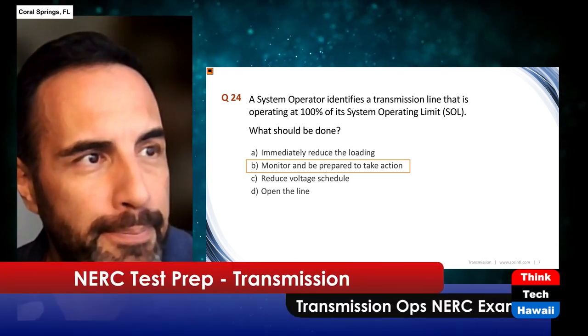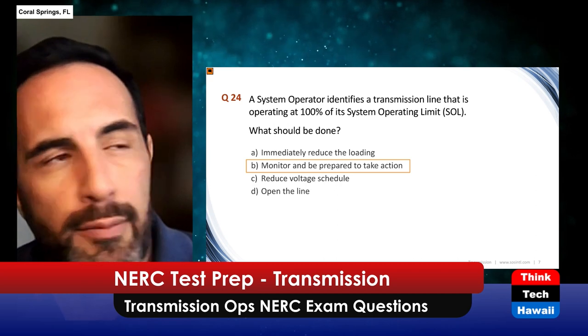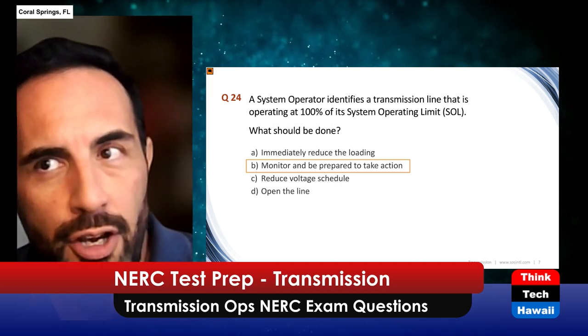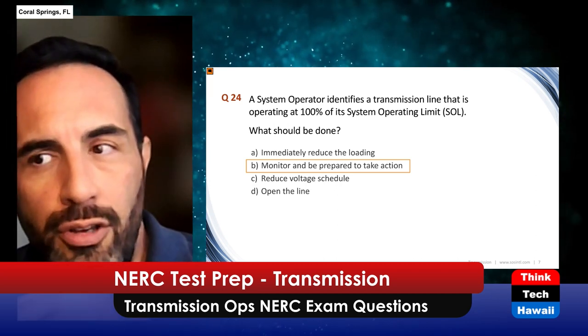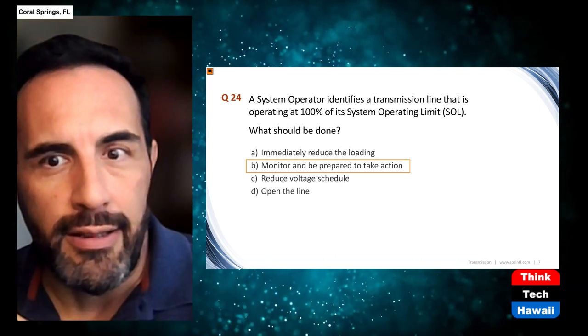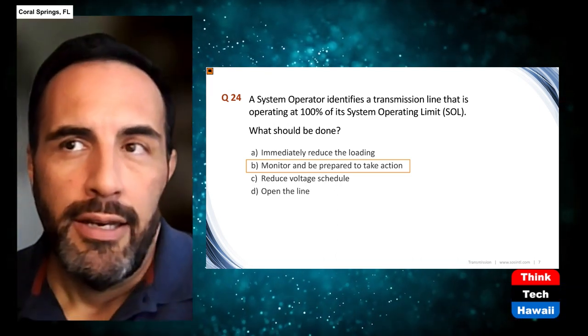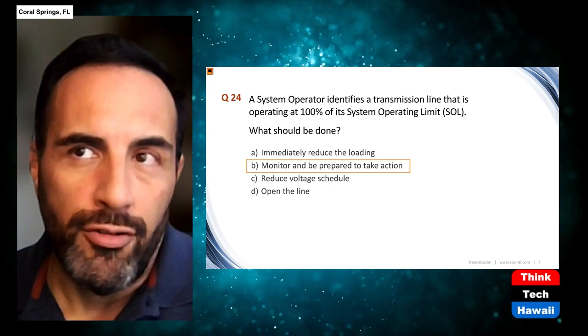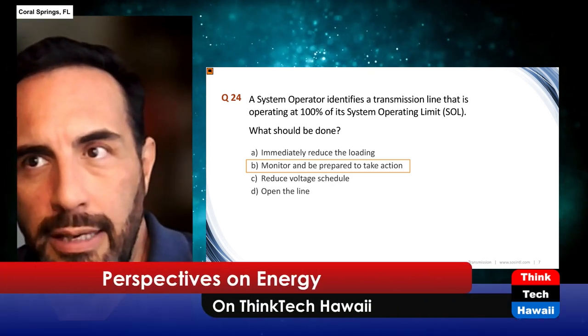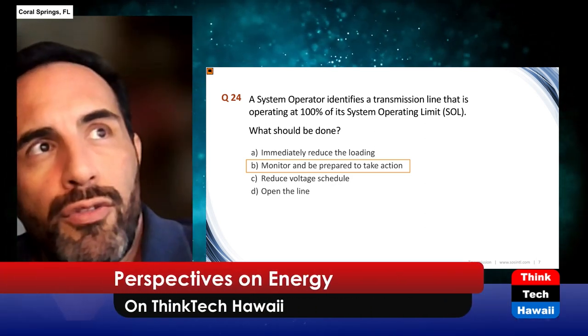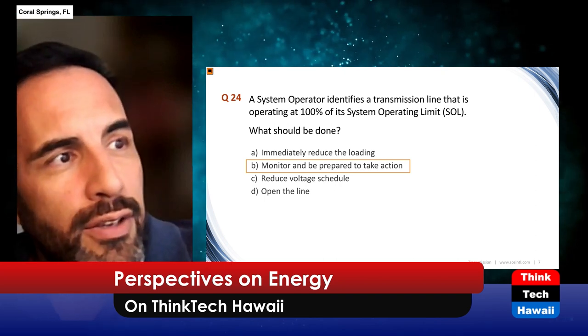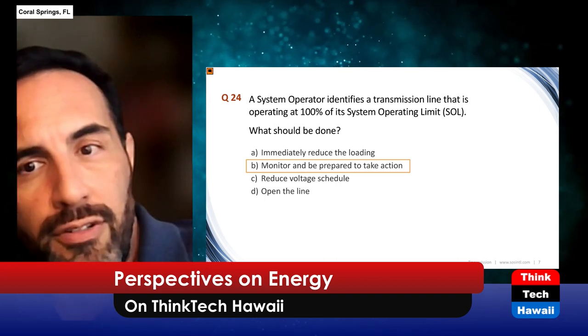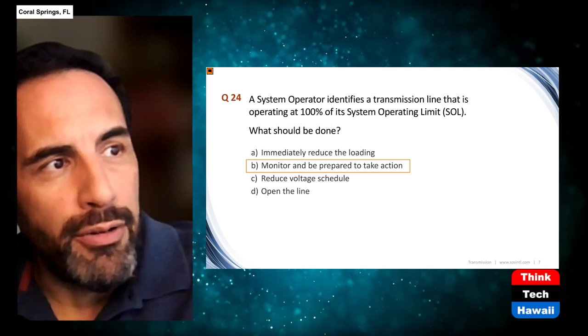So that's another example of something you don't want to be doing. So an important thing to understand, system operating limit means you're at 100%. Once you go to 101, now you're officially violating that hard limit on that line. Some places have short-term and long-term emergency ratings. Those vary. Now, again, this is probably post-contingency. This is already happening in real time.